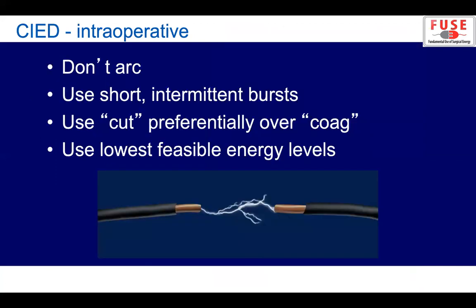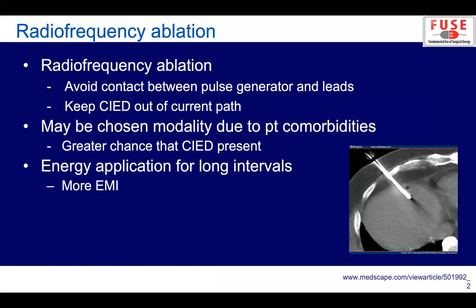How else can you mitigate some of the risk? Don't arc when you're using your device. Use short intermittent bursts. As I said before, use cut preferentially over coag, and use the lowest feasible energy levels. And that last bullet really should apply to any time you're using an electrosurgical device.